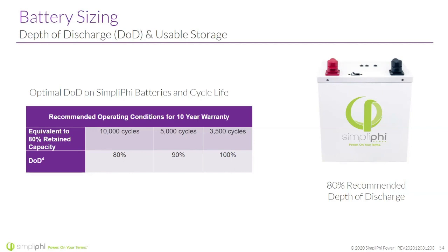So 10,000 cycles, that's the sales number that everybody says is 27 years, right? But we know in reality, sometimes the battery is going to be discharged 100%. You do that 100 times, not a big deal for a battery. Do that 3,500 times, that might be the end of life of the battery, right? And so it's important to keep in mind that batteries are most sensitive at high depths of discharge, and then sitting at high voltages and high temperatures. So if you keep those two things in mind, you are going to be experiencing between 5,000 to 10,000 cycles on your battery and be getting between 10 to 25 years. So don't abuse the battery, and the battery will last you a long time. Anyway, I took up time we didn't really have, so I want to let you wrap up, Chuck. Yep, here we go.